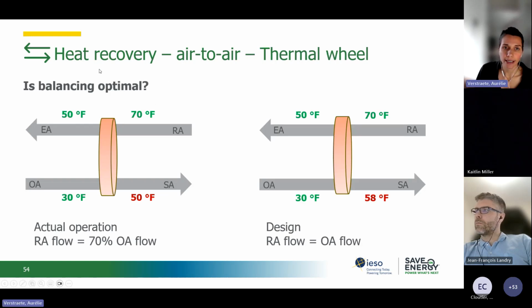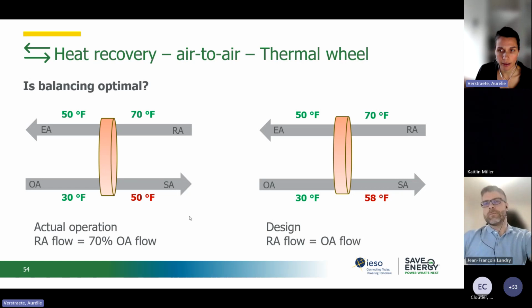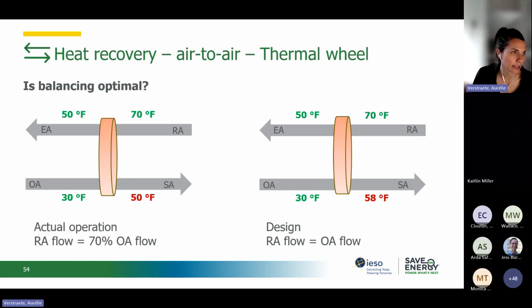The first question you can address is whether balancing is optimal. Here, in that scenario, you have a dedicated fresh air system with a thermal wheel. Comparing what you observe on site at left and what you expected during the design at right, based on heat recovery efficiency, you can conclude that balancing here is not optimal. Actually, the airflows have been reduced, the return airflow has been reduced, and it is very different from design. So here, at left, you don't reach the set point that you expected, and additional heating may be required to meet temperature set points.